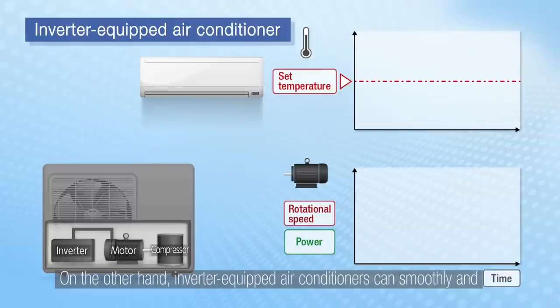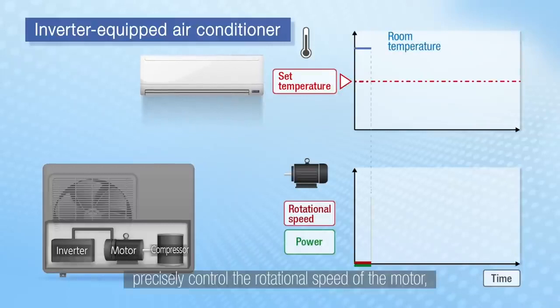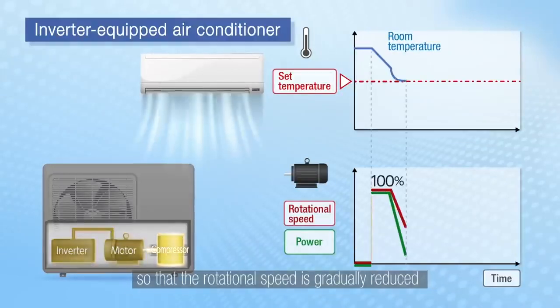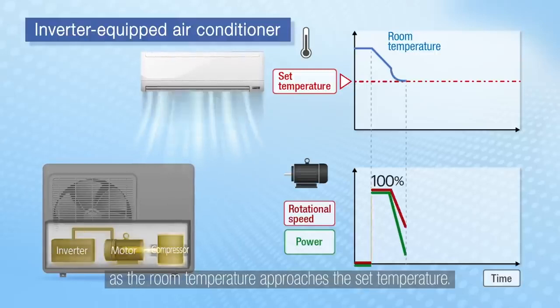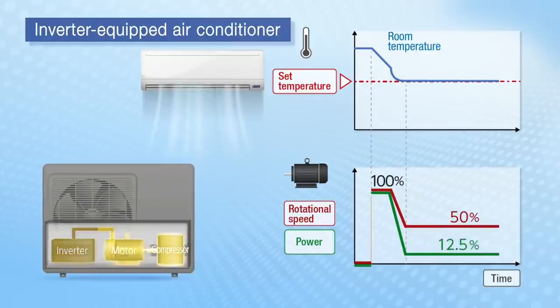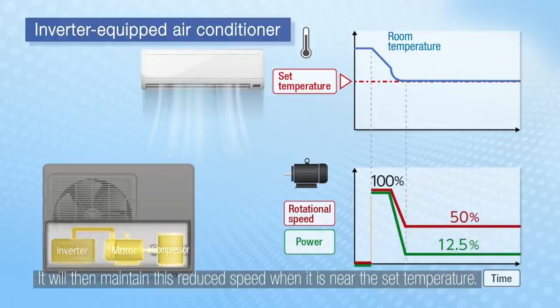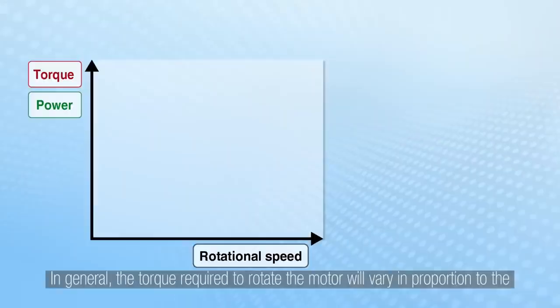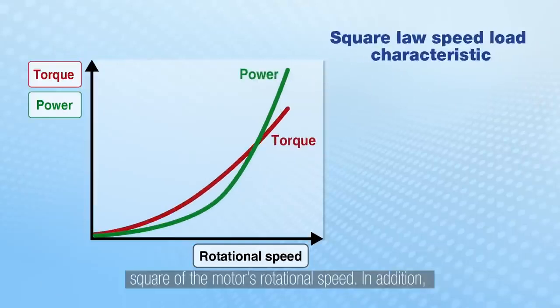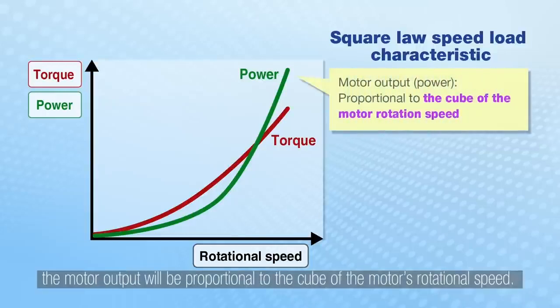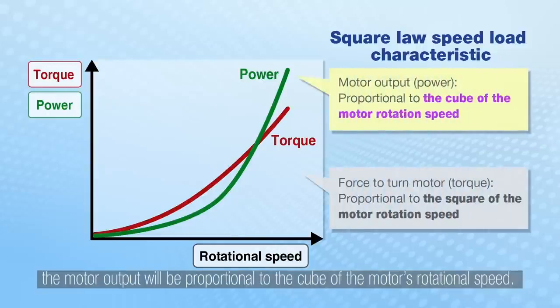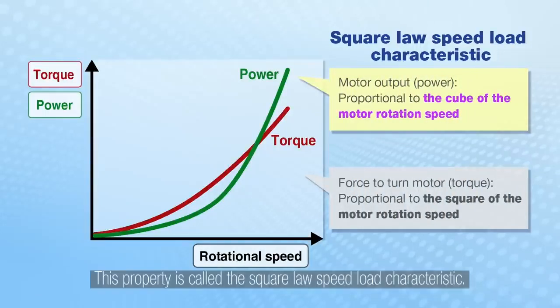On the other hand, inverter-equipped air conditioners can smoothly and precisely control the rotational speed of the motor, so that the rotational speed is gradually reduced as the room temperature approaches the set temperature. It will then maintain this reduced speed when it is near the set temperature. In general, the torque required to rotate the motor will vary in proportion to the square of the motor's rotational speed. In addition, the motor output will be proportional to the cube of the motor's rotational speed. This property is called the square law speed load characteristic.